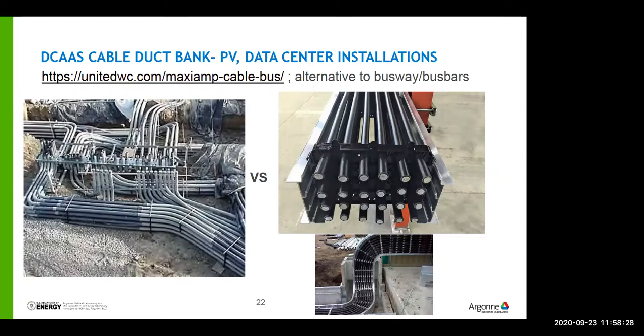This is basically what real people do. They say, I have megawatts of photovoltaics. How do I connect all these things affordably? You just don't see a ton of conduit coming off a PV array. You'll see this thing. It's an aluminum frame that has some plastic discs that hold the conductors away from each other. As you can imagine, if you bundle it in a conduit, you get less performance because you have to derate for heat. But when you spread it apart with a mesh cover over the top and the bottom, I let all the heat go right through.